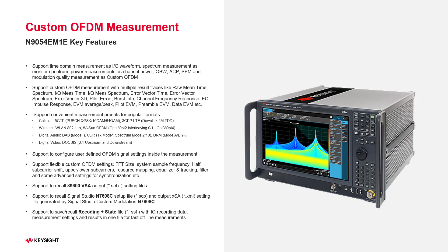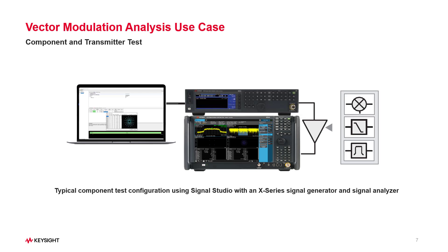You can also demodulate pilot, preamble, and data EVM separately. It supports convenient measurement presets for the latest popular formats in cellular like 5G TF, wireless network like Wi-SUN OFDM signal, digital video and radio like DOCSIS. We are constantly working to update and enhance this software. You can utilize these latest features to do fast flexible custom OFDM measurement and troubleshooting, such as recalling Signal Studio custom modulation setup files, and saving recording and state files. VMA application is able to accelerate your design first to market.